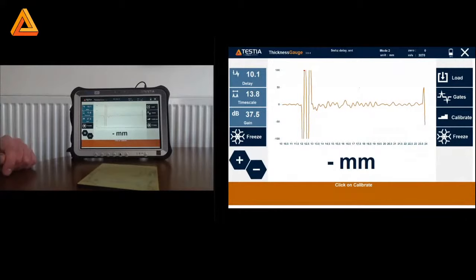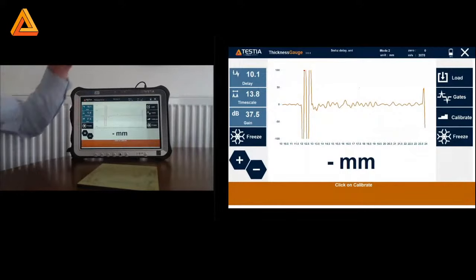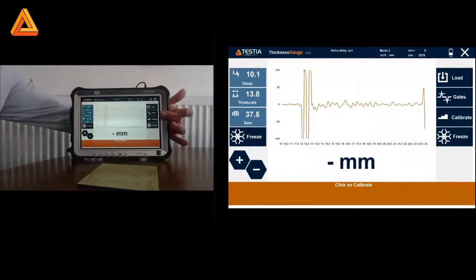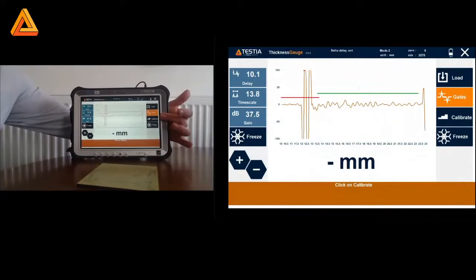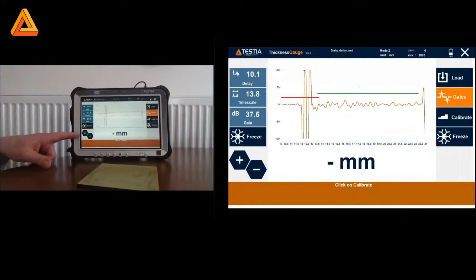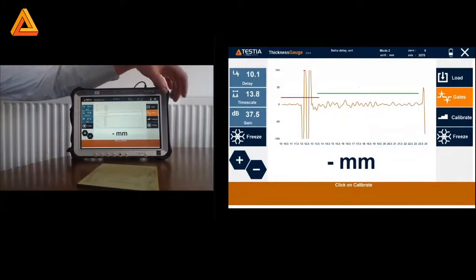The thickness gauge is an icon-based module, so down the left-hand side we have the ability to manipulate the A-scan positioning, and on the right-hand side we have the ability to switch our gates on and perform a two-step calibration. The freeze button is on both left and right, depending on which hand you have available, and we have a plus and minus for making incremental changes to any screens.